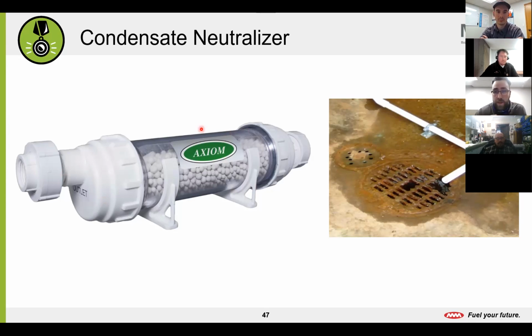We'll see this tube of white pellets. That's actually a neutralizer. A lot of times you'll see it as these white pellets, or we may have a bucket of limestone rock on site that the water will go through, and we can actually test this water coming out of the drain. And if it comes back too acidic, we can swap out those rocks or those pellets with some new stuff, and that's going to help get rid of that acidity, treat that water, and make sure we're not damaging the surfaces that this water is coming in contact with.